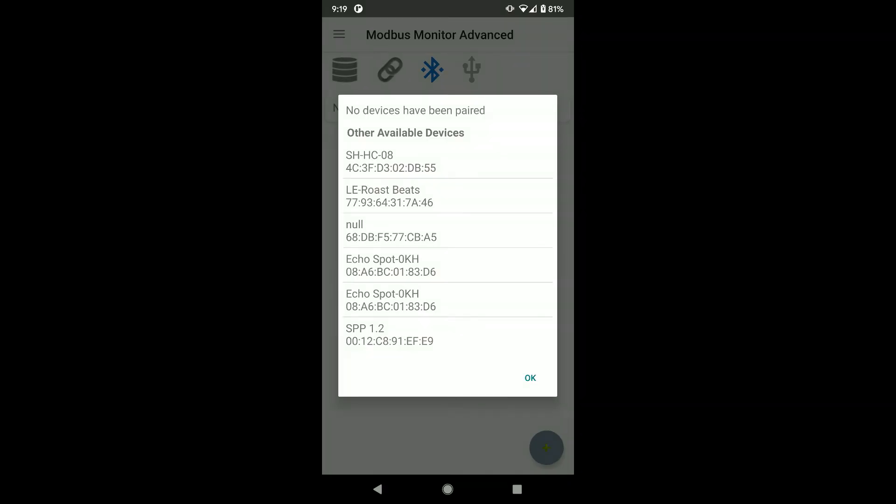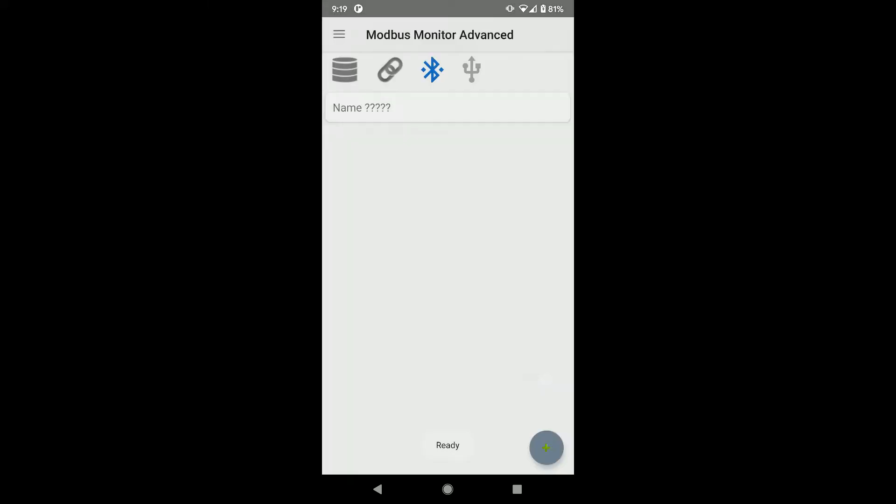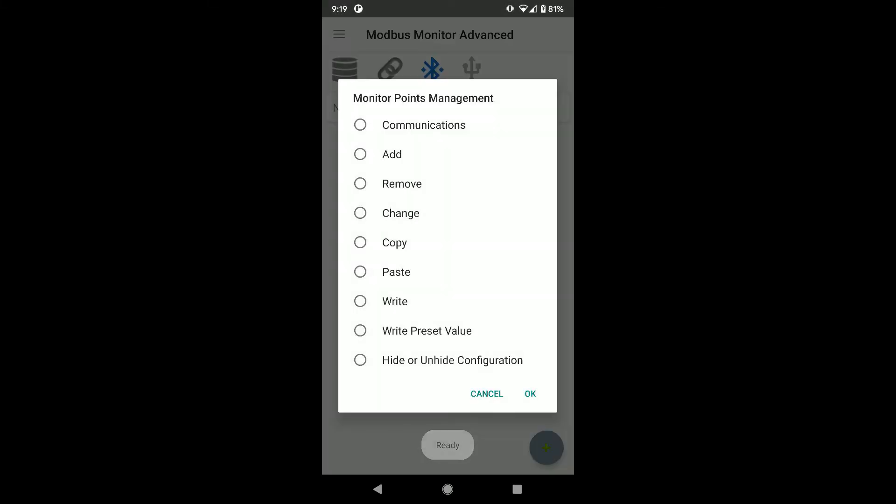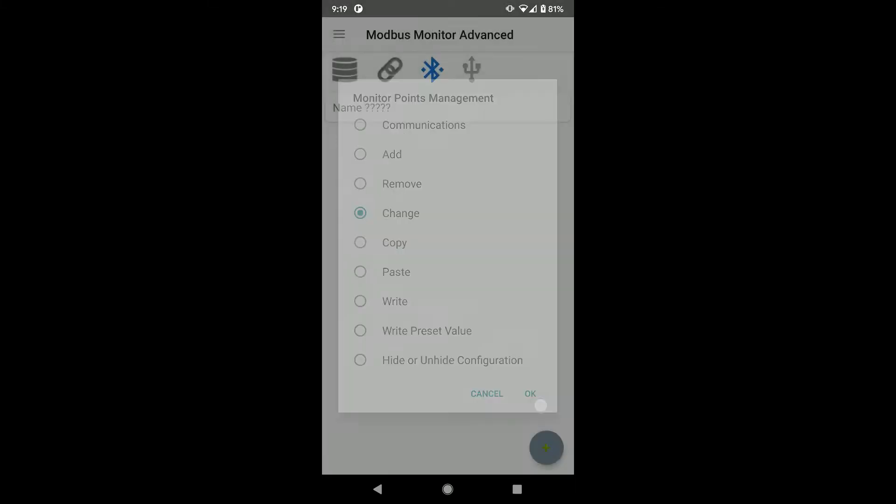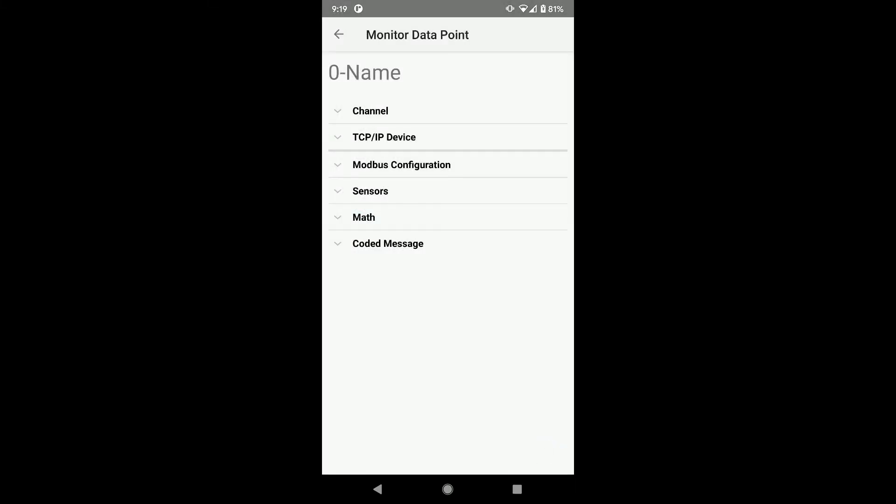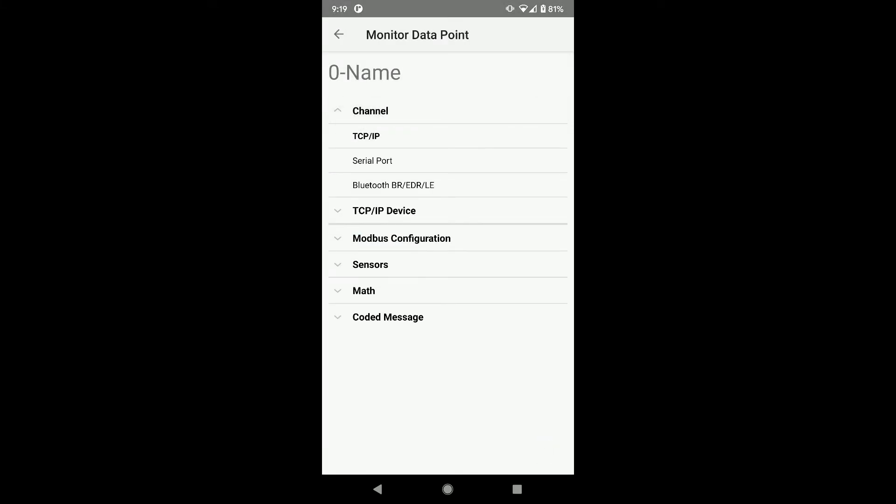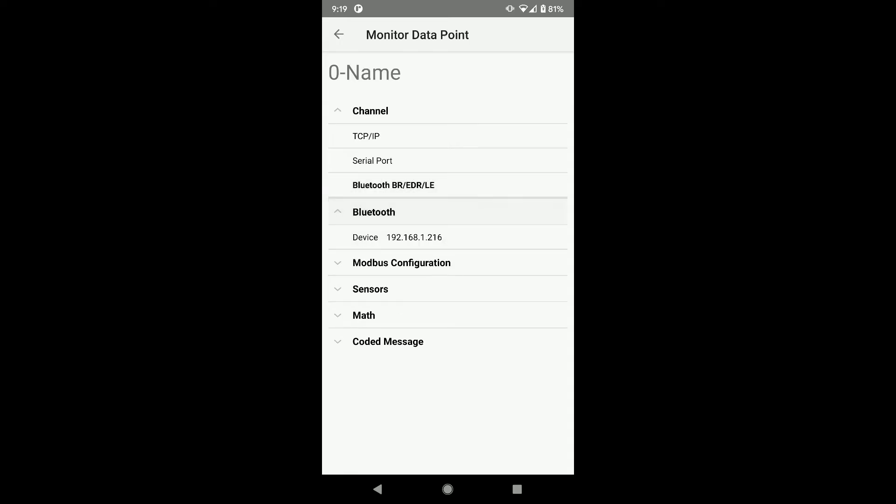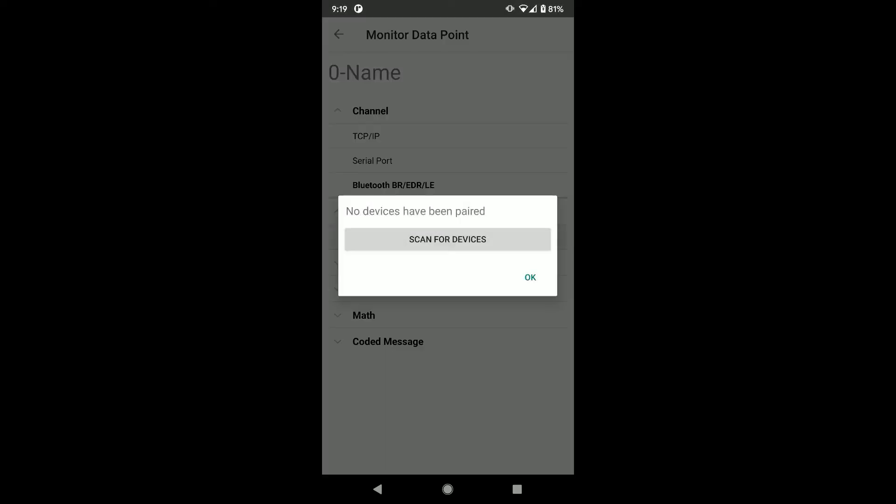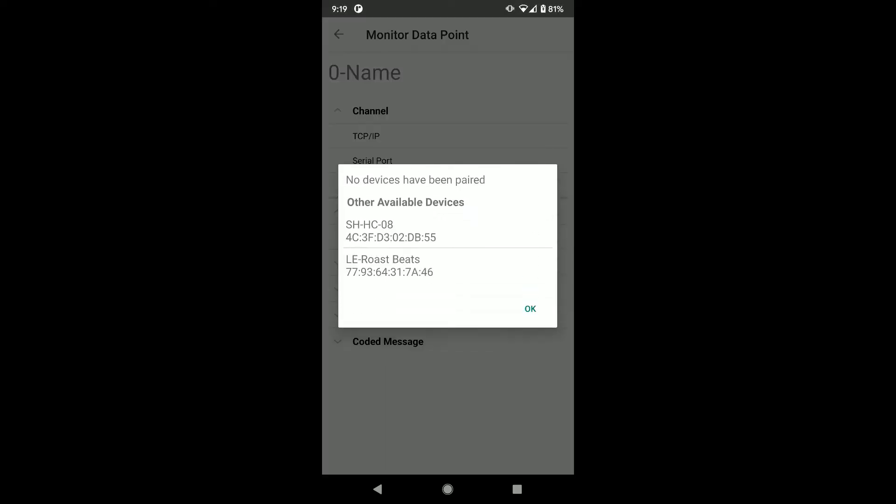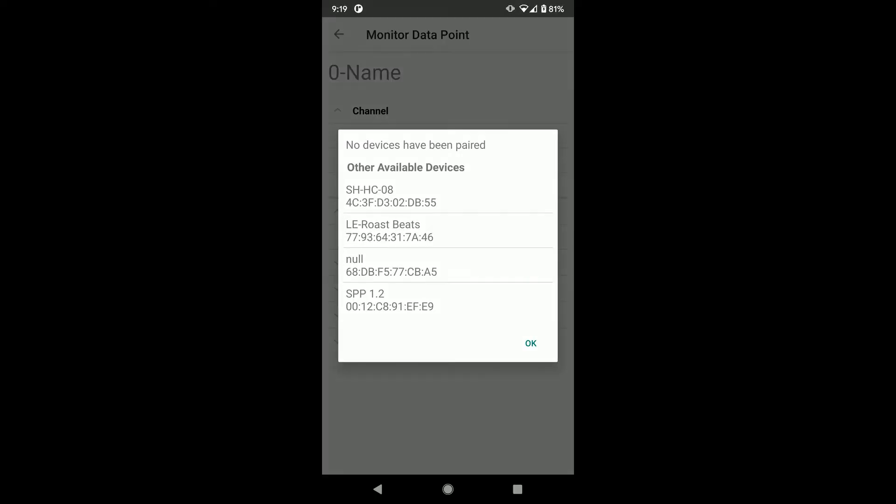Alright, looks like I am ready for communication. Let's set up the Modbus point to use the Bluetooth channel and program the MAC address on my Bluetooth device. Click on the monitor point and choose Change. Click on Channel option and choose Bluetooth. Now click on the Bluetooth option and click on the device address.